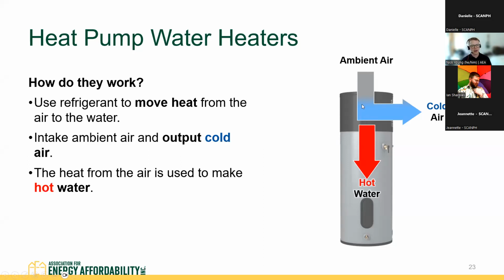So the air gets cold—it outputs cold air—and the water gets hot. So what you get out of a heat pump water heater is hot water and cold air. That's really important to know: heat pump water heaters generate hot water, obviously, because that's the whole point, but they also generate cold air. So you have to know, what are we doing with that cold air? Where is it going, and where is my heat pump water heater?